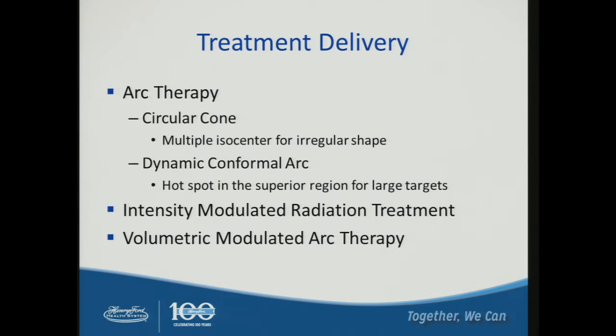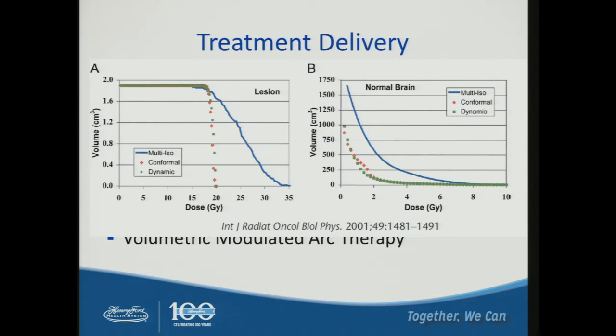Arc therapy is really the gold standard for LINAC-based brain treatment. In the old days, circular cones were used a lot, which work well for spherical targets with very good conformity. The challenge is for irregular shapes, where multiple isocenters lead to hot spots at overlaps and significantly higher normal brain dose. Dynamic conformal arc has been used for radiosurgery for the last decade — the MLC dynamically conforms to the target as the gantry rotates, achieving very good conformity for irregular shapes.